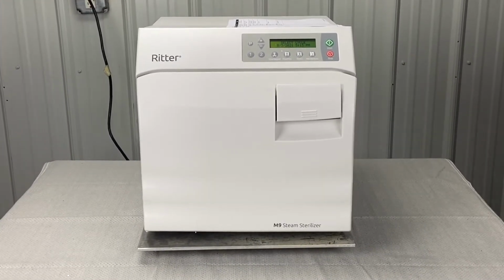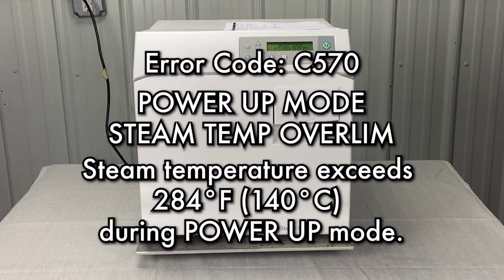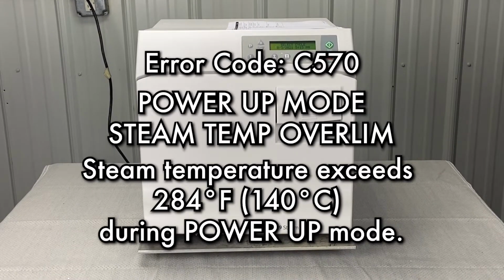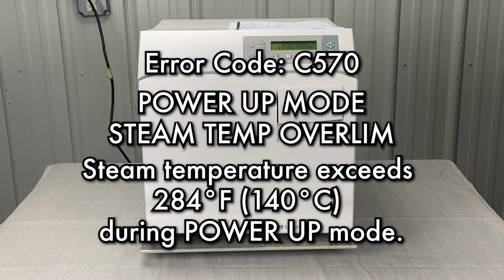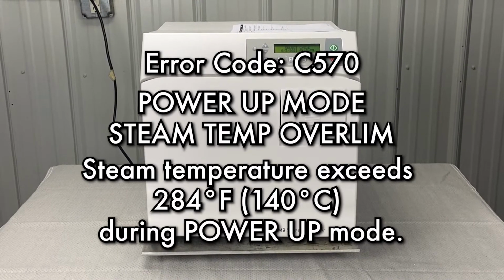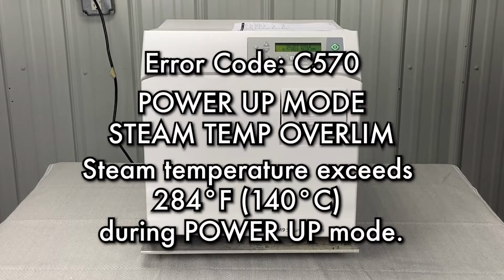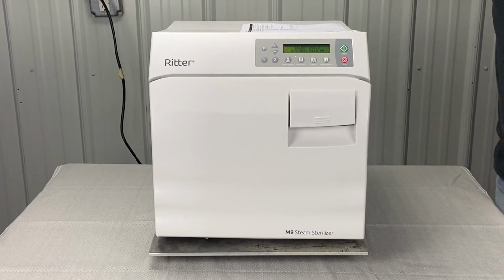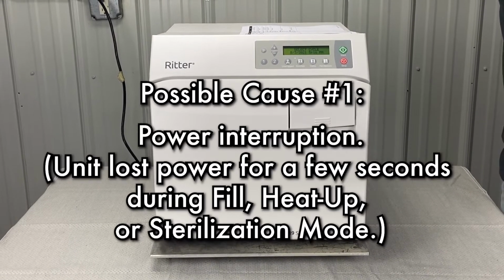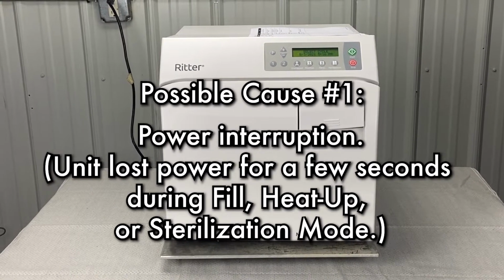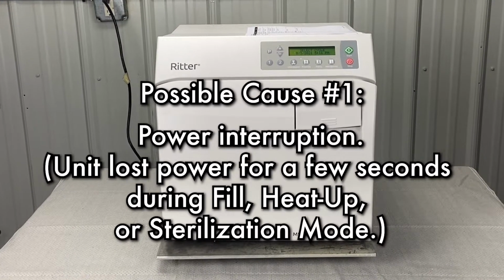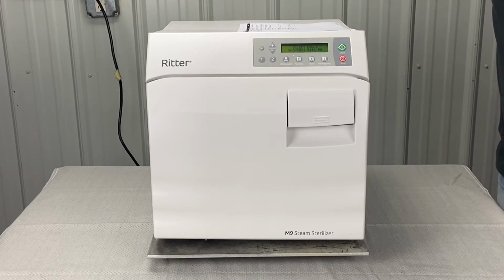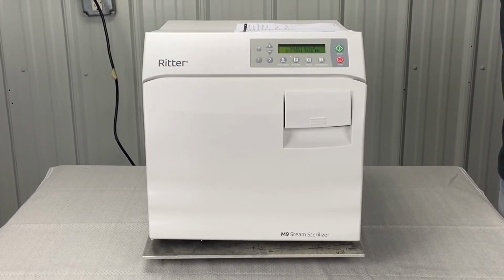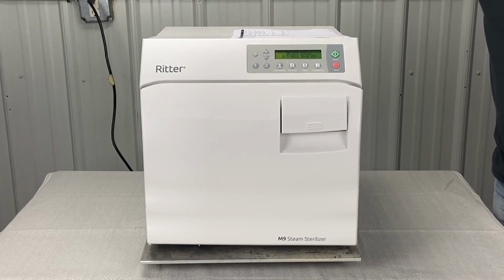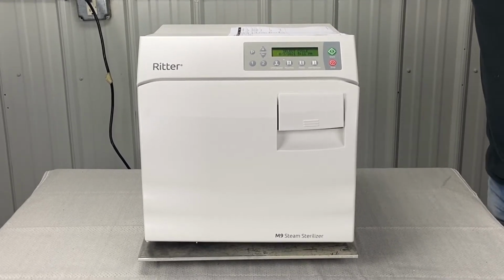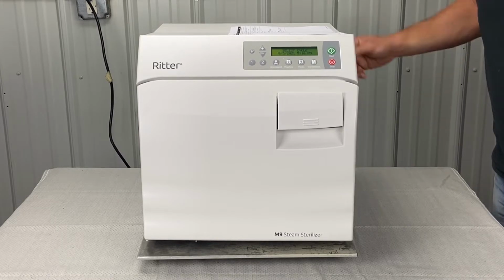We're talking about error code Charlie 570. Power up mode error, steam temp over limit. Steam temperature exceeds 284 degrees during power up mode. So the cause would possibly be a power interruption. Unit lost power for a few seconds during fill, heat up, or sterilize mode. Check power cord connections. Power interruption could be due to an electrical storm or brownout, etc. Secure power cord connections at wall, outlet, sterilizer, or receptacle.